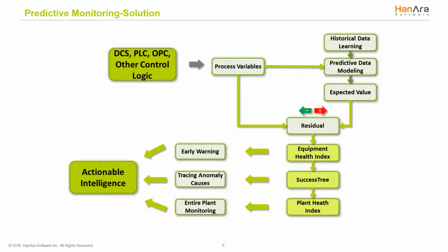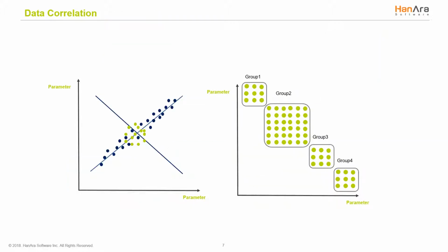For example, the bearing temperature and vibration in a turbine and the temperature and pressure in a turbine shaft are all related signals, so they can be grouped into a turbine group. Other signals may be grouped together when they are designed to automatically or manually adjust to prevent drastic increases or decreases. Finally, general properties should be considered, like the relationship between flow rate, temperature, and pressure. Once completed, the selected data reflects the physical and empirical properties of the signal itself. Through this process, a series of groups are created.